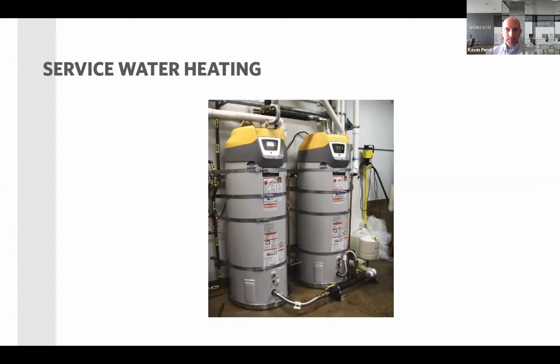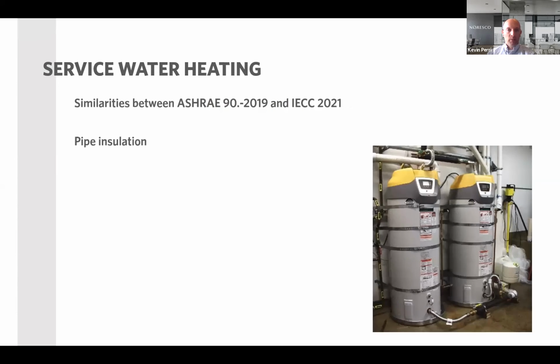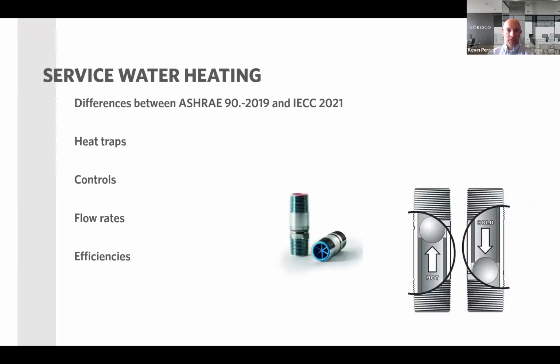So let's jump into service water heating. Similarities between ASHRAE 90.1 and IECC 2021: pipe insulation thickness. It's the same thickness on your piping insulation no matter which pathway you go down. Differences, there are a lot more. Heat traps. ASHRAE says that heat traps are needed only if they aren't integral heat traps and the system is non-circulating. IECC says that it has to have integral heat traps. So there are some differences there for service water heating. So this is your domestic water heating on heat traps.